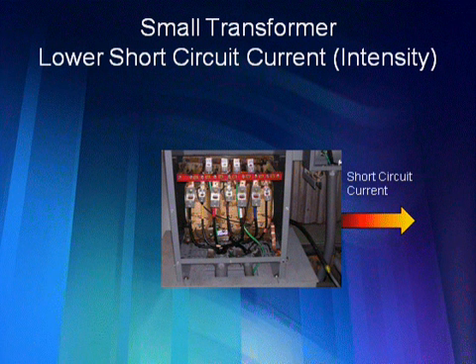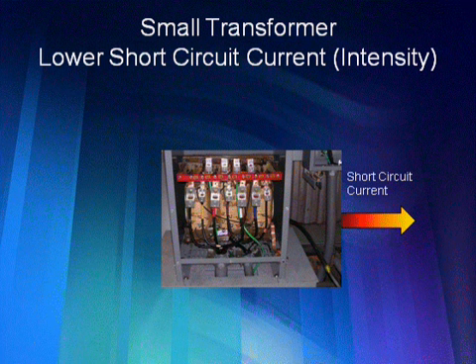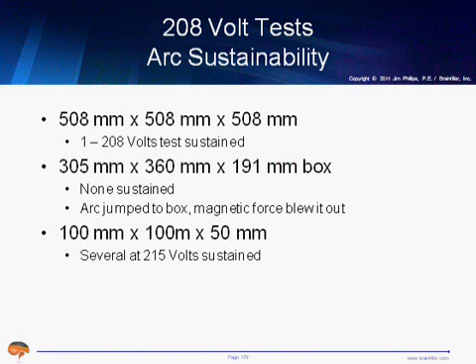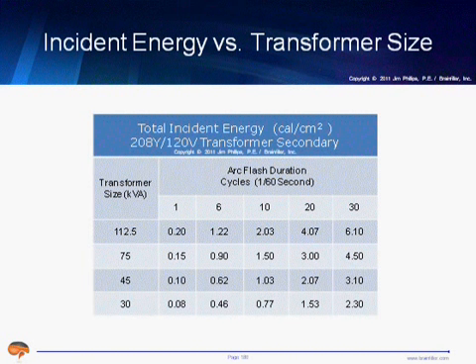And the way the IEEE equations are configured right now, if you have a low short circuit current and your upstream protective device, which is sometimes the transformer primary, may not respond fast enough, you have a low current with a long clearing time, and you can end up with some pretty large values. Well, some of the research, and some of this was done back with the original 1584 tests, shows it depends on a lot of things whether or not you can actually sustain a low current, low voltage arc flash. It depends, for example, on the size of the enclosure. You can sustain a lot easier in smaller enclosures. It depends on the orientation of the bus. It depends on the insulation. It depends on whether you're terminating into barriers or not.